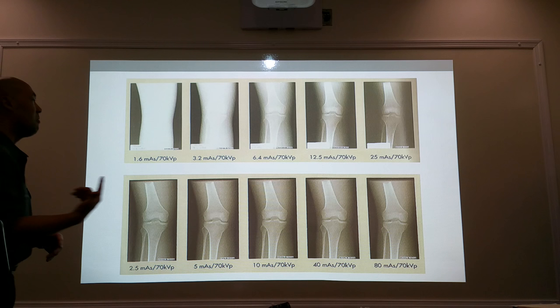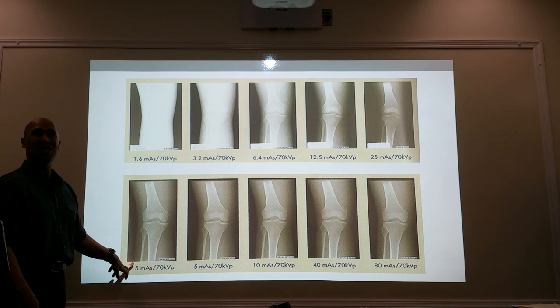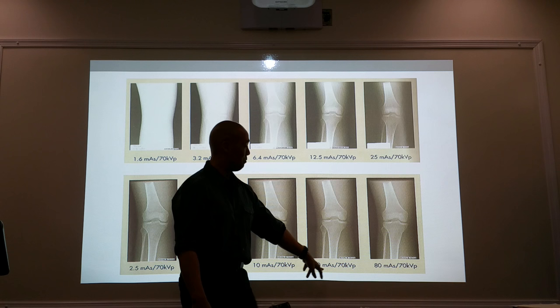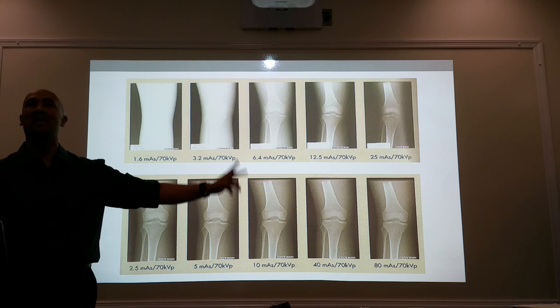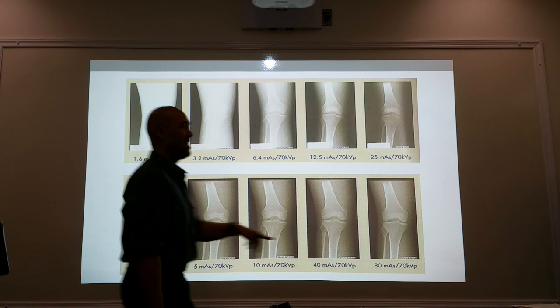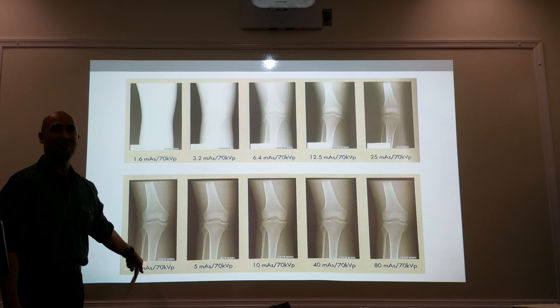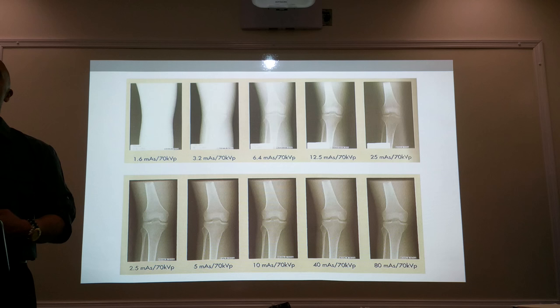Here is the same study with computerized radiography. At 2.5 mAs it looks good. We doubled it to 5 — looks the same. Doubled 5 to 10 mAs — still looks the same. Then 40 mAs, then 80 mAs. We went from 2.5 to 80 — this is almost 35 times the patient exposure. We could be killing our patients and not know it because the images look good every time. Your 80 mAs looks just as good as your 2.5 mAs.